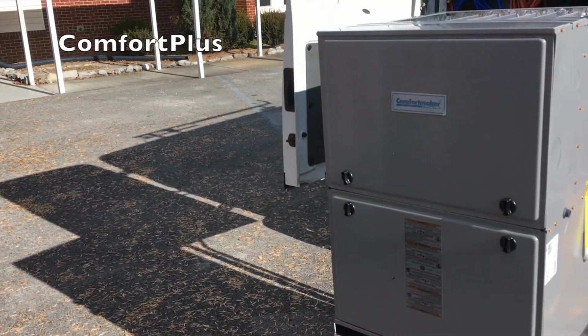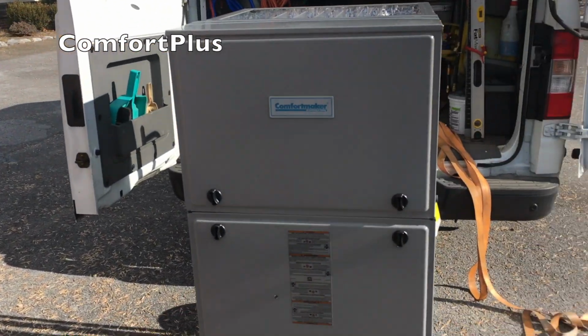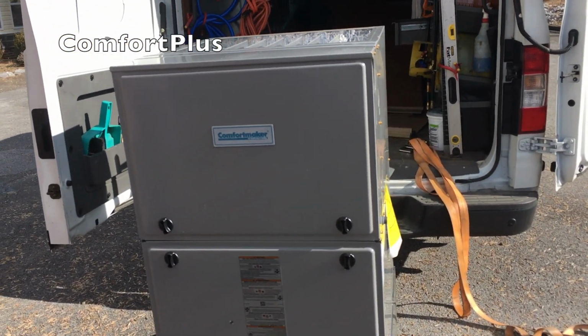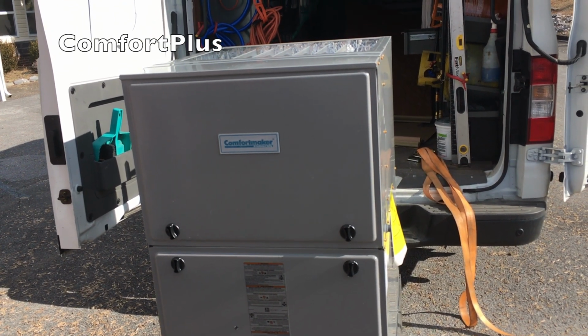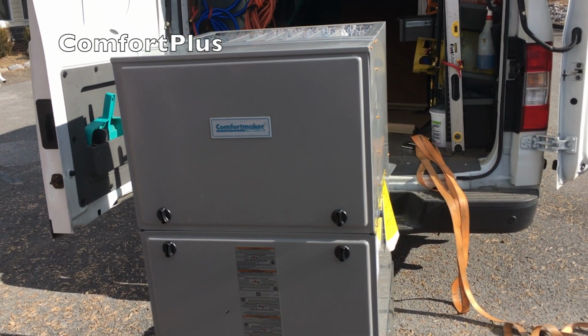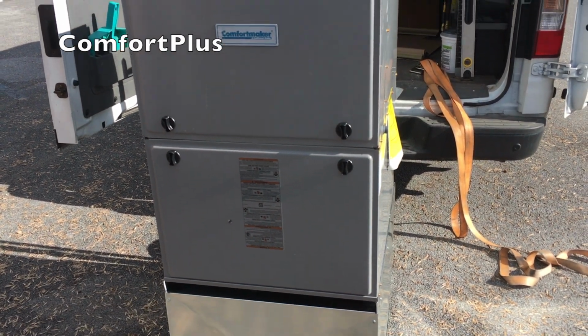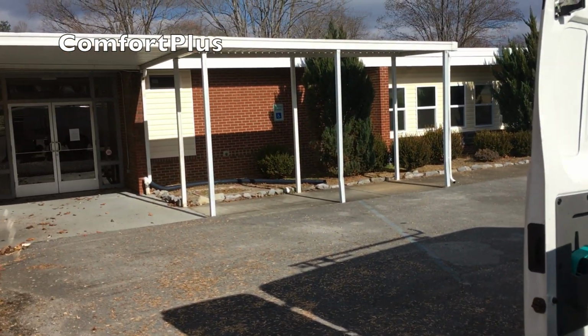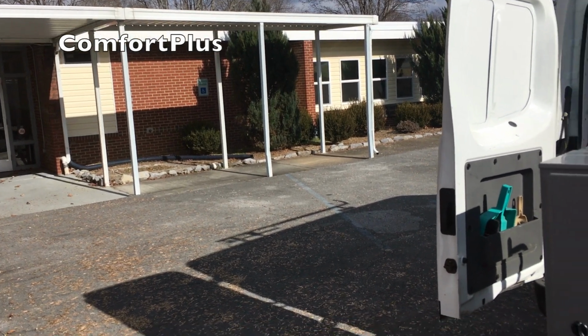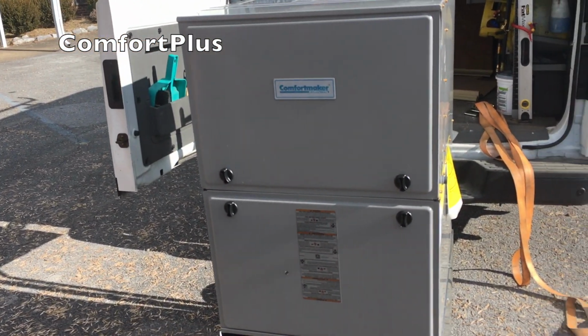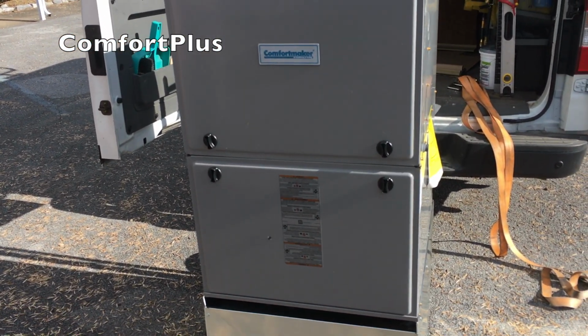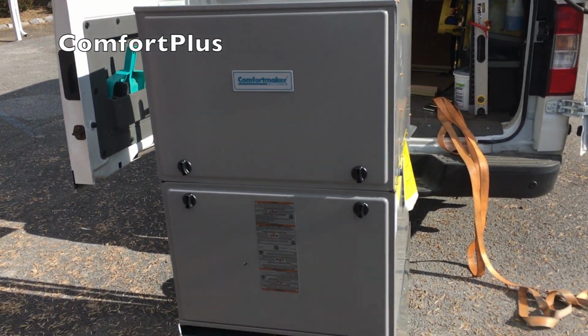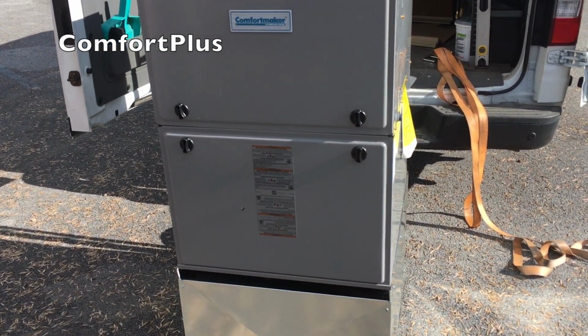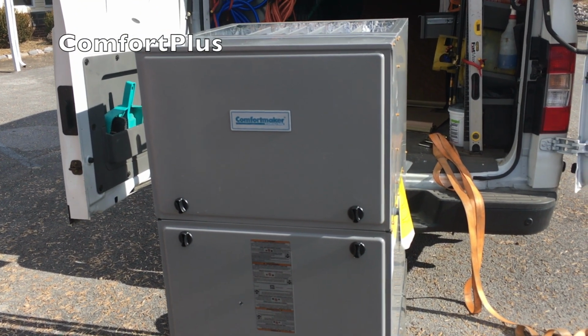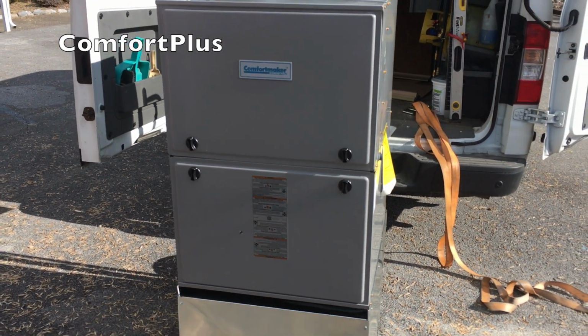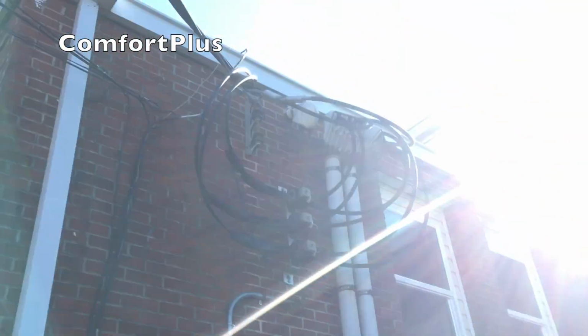I didn't mention earlier, the boiler's no good. It's one of the reasons we closed the school. It was made in 1978, it's an atmospheric boiler, and we were forever coming over here cleaning the tubes off where the rust was falling down on them, so they're not going to keep it. They've already mostly got electric heat in the rest of the school now. I think we have an 800 amp service, so they're not going to replace that boiler. We're just looking for some way to get them a little bit of heat in the gym to keep it manageable in the wintertime and warm it up a little when they want to come play basketball. Here's the back of the school.